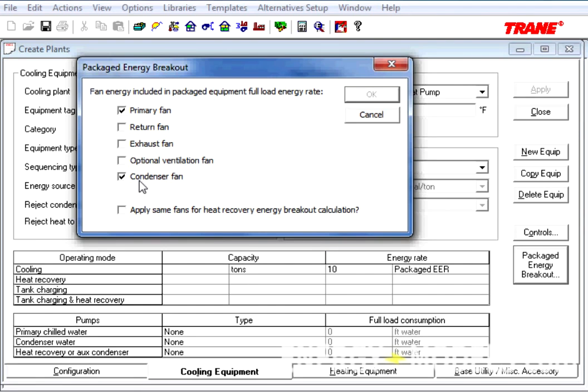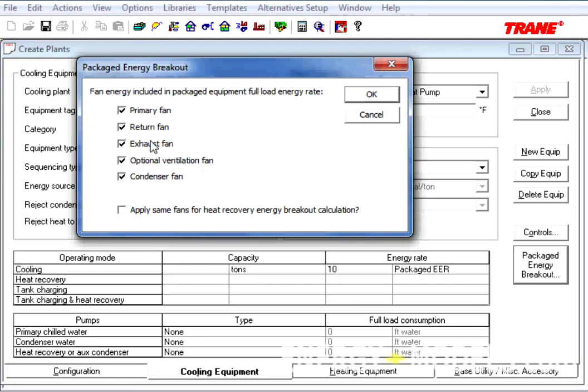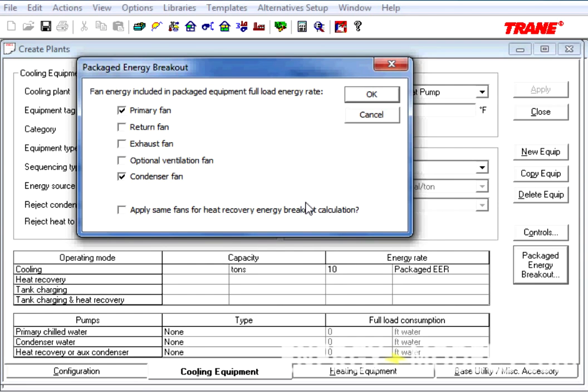But it also might be a return fan, an exhaust fan, and an optional ventilation fan. So, all you'll need to know now is what fans were included in that energy rate, rather than pulling out some hair and figuring it out yourself by doing the previous method of breaking everything into kW per ton and subtracting out these individual variables yourself. So, now you can put the nominal Packaged EER or Packaged COP on your Air Cooled Unitaries, Water Cooled Unitaries, or Water Source Heat Pumps in Trace.